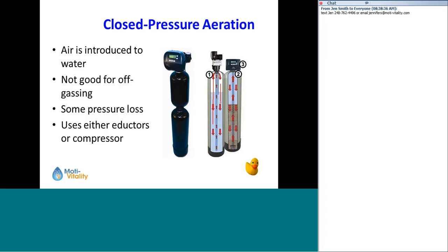Low levels of hydrogen sulfide will use air. Higher levels, you're going to need some sort of chemical oxidizer like hydrogen peroxide or chlorine to help with that. But basically, this first tank converts it, and then the water flows through, and you have a filter media which then filters out everything. And it's going to be on a timer. Usually you'll backwash every 3 days.